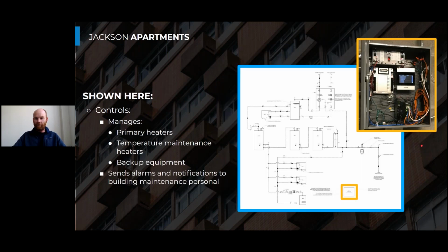And we also have a control system here, and we're using a third-party control system because we're tracking the energy efficiency or the energy performance of this system, as well as a few other things. Like email alarms, routine maintenance calls, and just overall health checkups on the system that third-party controller allows. It can communicate with the internal Colmac controls, so we can actually extract a lot of data from that Colmac heat pump and look at it remotely on the cloud.